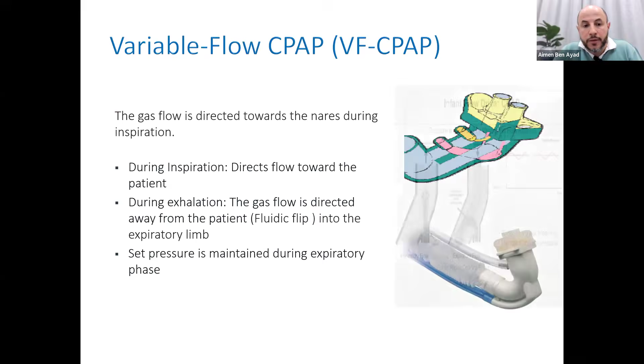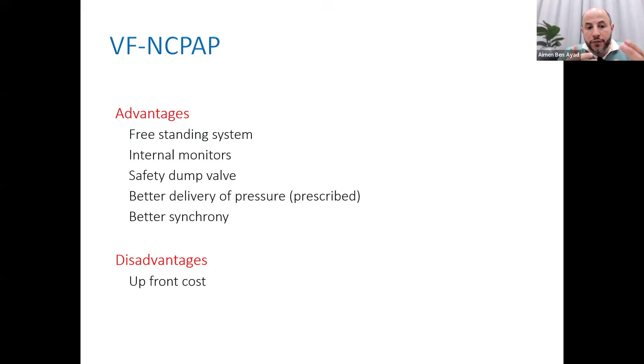So the advantage of the variable flow CPAP is that the set is free standing. You can move it from one baby to another. You don't need to use a ventilator. It has an internal monitor, so in case the baby is apneic or disconnected, there is an alarm system. The battery is built in, and there is synchronicity. It helps the baby breathe comfortably. Disadvantage: it's the upfront cost.